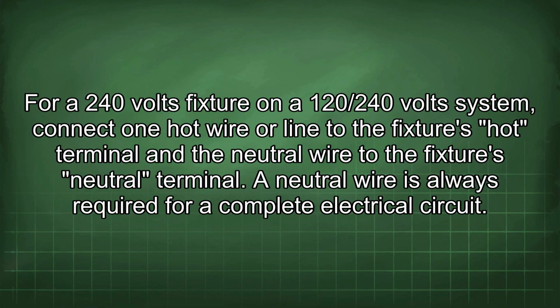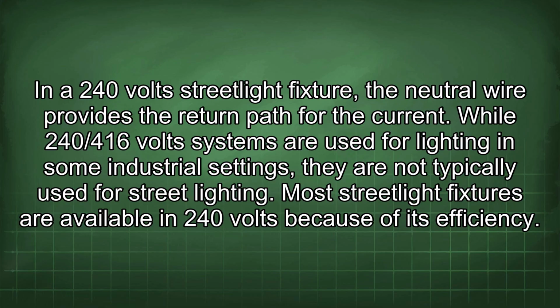For a 240 volts fixture on a 120/240 volts system, connect one hot wire or line to the fixture's hot terminal and the neutral wire to the fixture's neutral terminal. A neutral wire is always required for a complete electrical circuit. In a 240 volt streetlight fixture, the neutral wire provides the return path for the current.